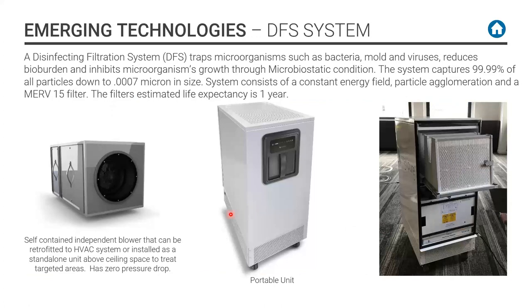Other technologies: in small rooms, conference rooms, etc., we're recommending air cleaners, HEPA filter type cleaners, and we've researched a number, and this happens to be one. This is a shot from my office, where this particular manufacturer uses a DFS system, which is basically a HEPA filter in a V bank, but they put an electric charge across the filter bank. They claim these high ions attach themselves to particles and get trapped in the filters, and they claim it's good down to 0.07 microns in size. These are expensive units, but somewhat effective.